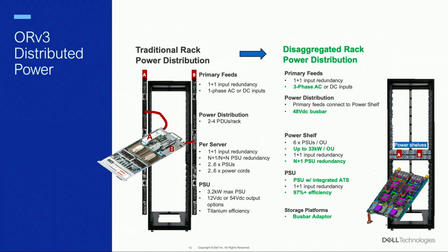So traditional racks for HPC typically have 2, 4, or even 6 single or three-phase PDUs. Each server has multiple PSUs. We can reach up to 3.2 kilowatts per PSU, even if they have titanium efficiency and are used in a redundant mode, which could be 1 plus 1, n plus 1, or n plus n. This adds complexity and doesn't really scale well because there is a lot of over-provisioning in the PSUs.